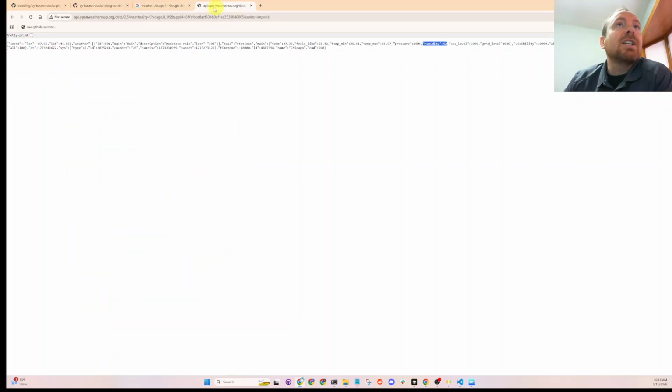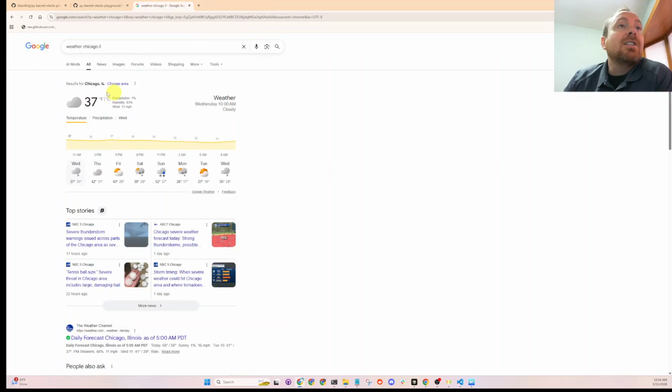Even though we're getting data from the OpenWeatherMap API, this could be the very same weather station at some airport in Chicago, I don't know. The point is, more than likely this weather is much more accurate, hopefully, than the local flimsy building automation sensor. Those sensors are notorious for being installed in very poor places, where the sun shines on them and they read erroneous values.